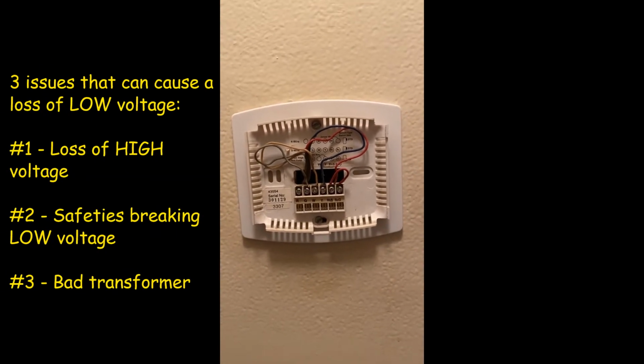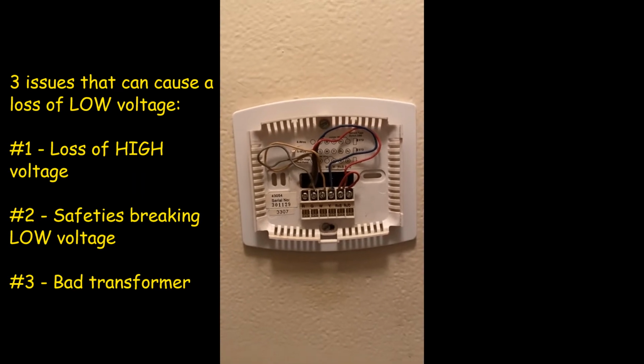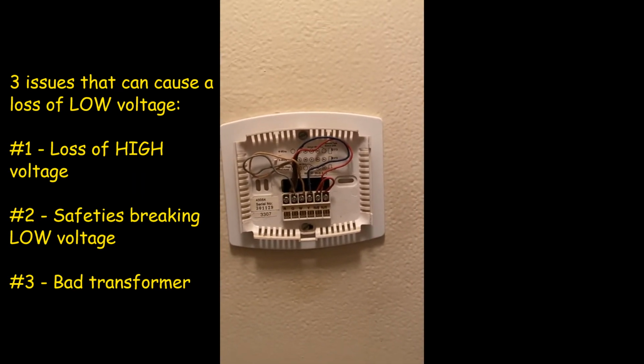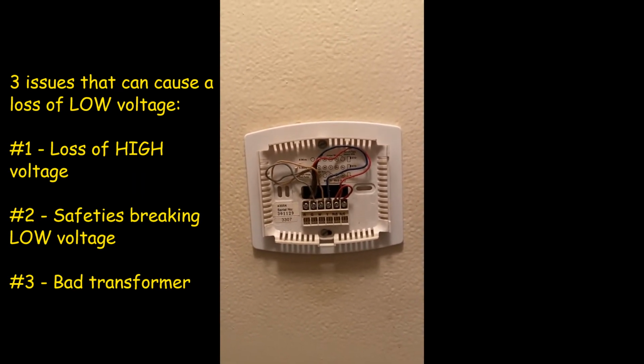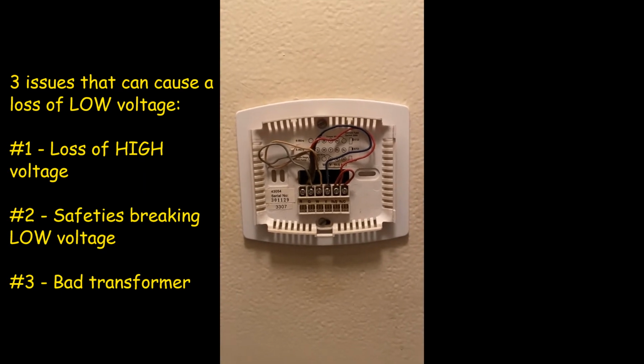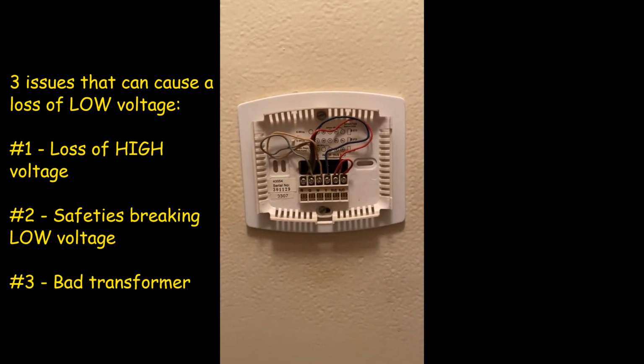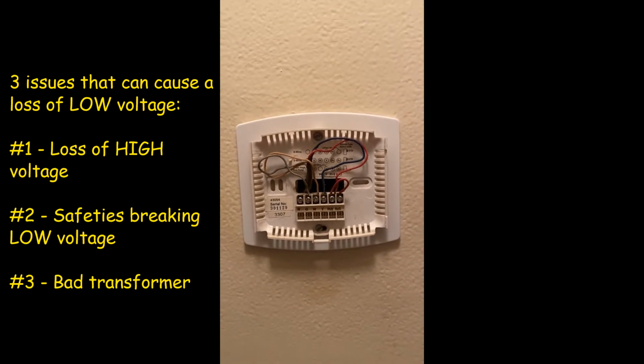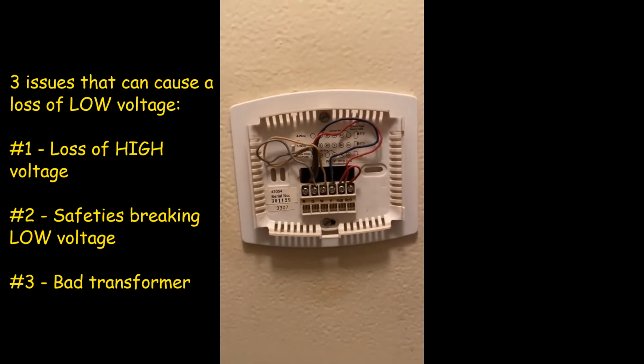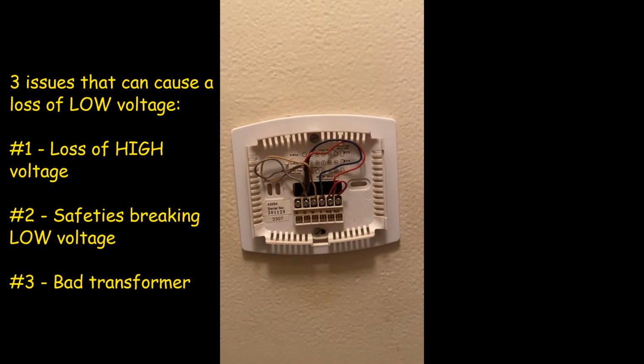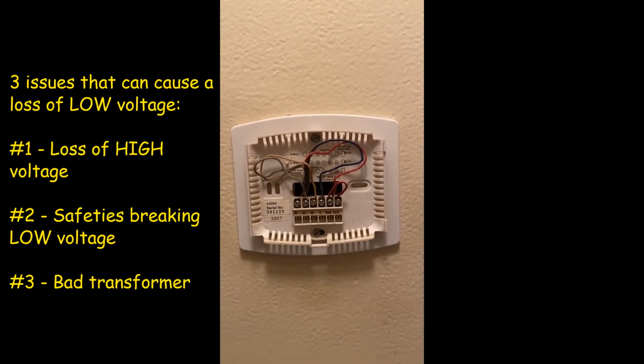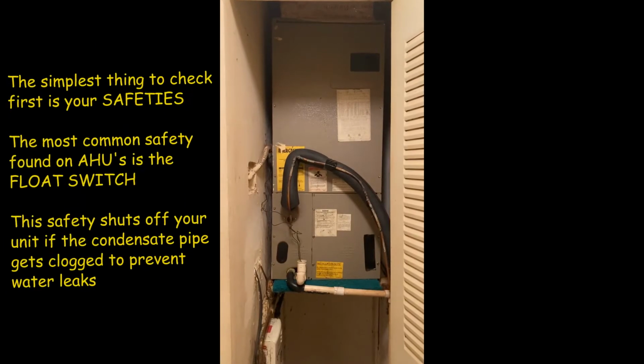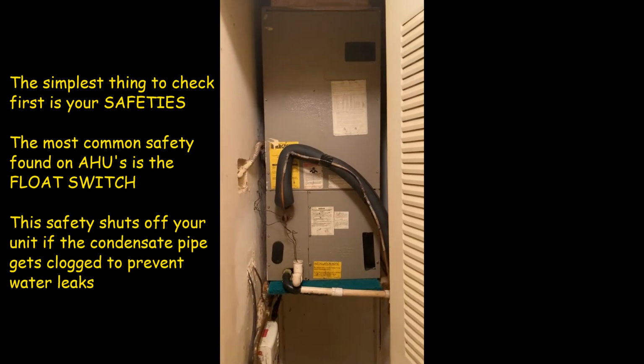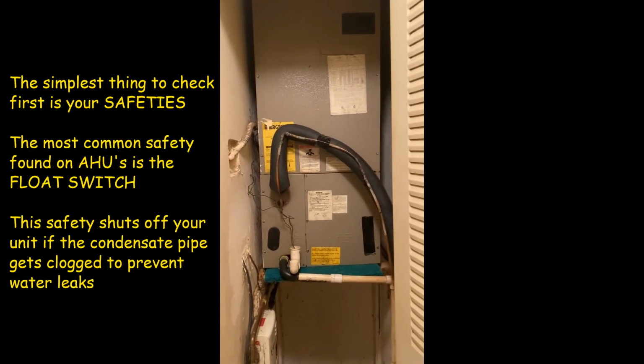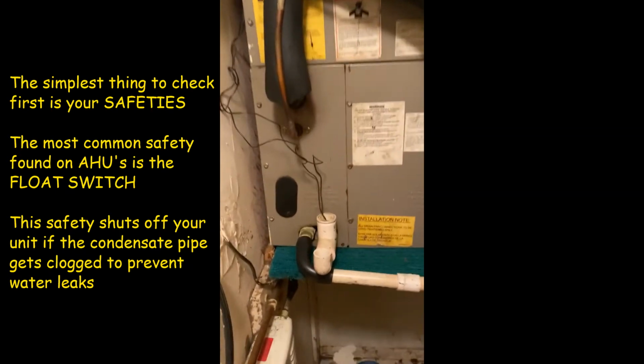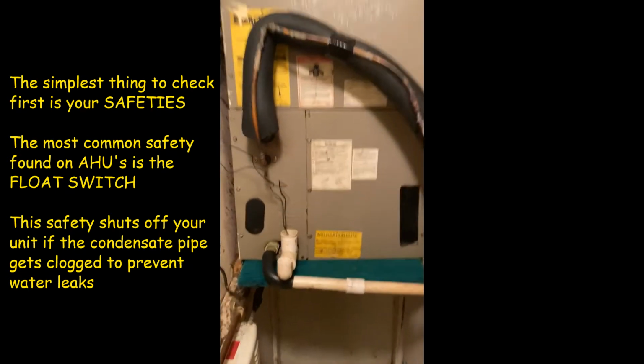So let's say you don't have 24 volts here at the thermostat. Now what? What does that tell us? That tells us that you either do not have high voltage, or your safety is breaking your control voltage, or you just have no control voltage. So let's take a look. So the simplest and most obvious thing to check first if you don't have low voltage or control voltage is your safeties. Some units just don't have any safeties.